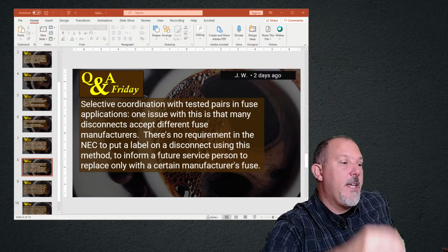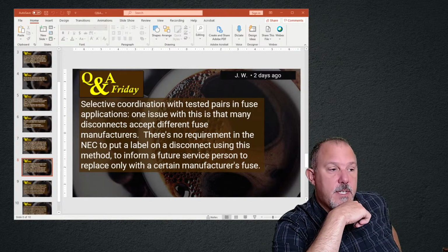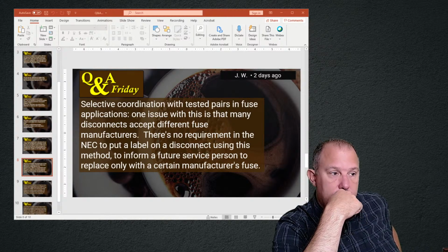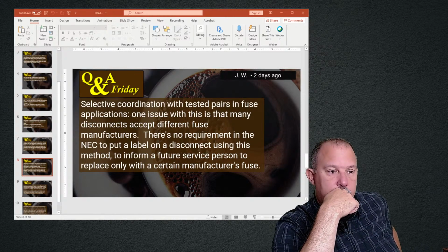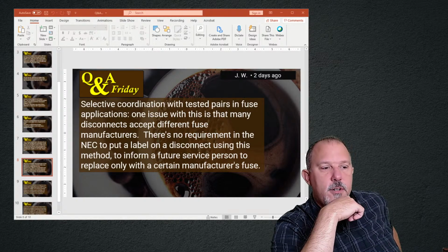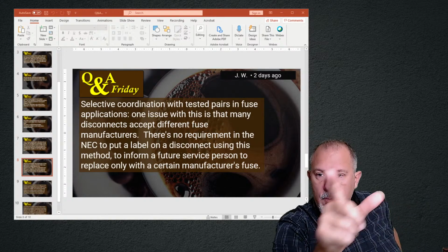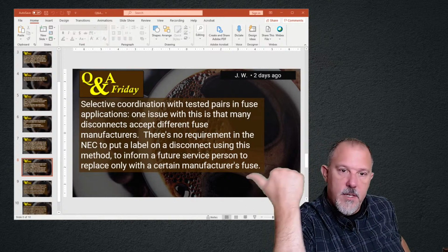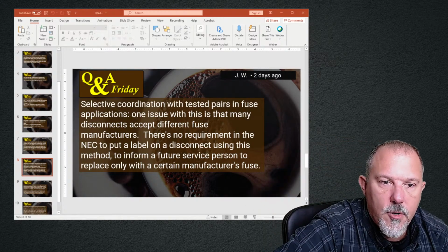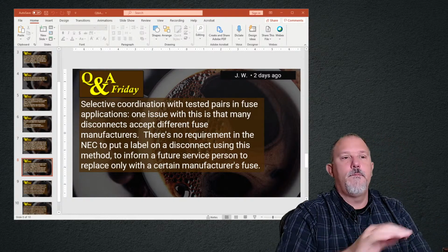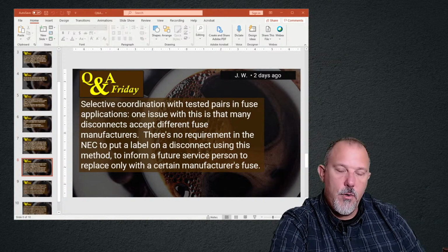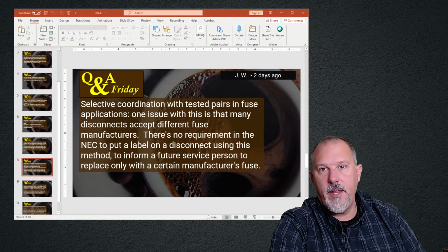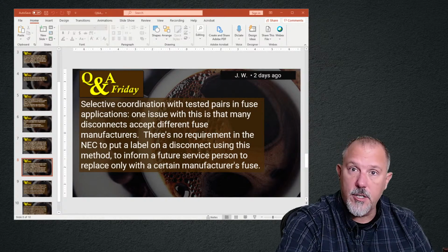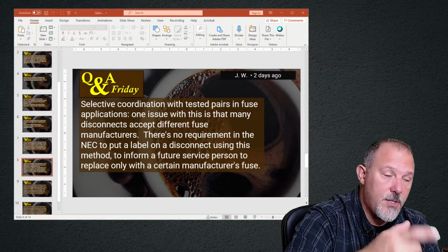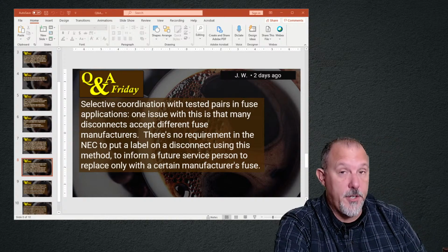Modifications. Where modifications, additions, or deletions to the emergency system occur, selective coordination of the emergency systems overcurrent devices with all supply side and load side OCPDs shall be reevaluated. So to this gentleman's point, there's no requirement. Now, be mindful. Yes, fuses can be replaced by different manufacturers. I could even put a different catalog number fuse from the same manufacturer into that slot, which would be ungood.